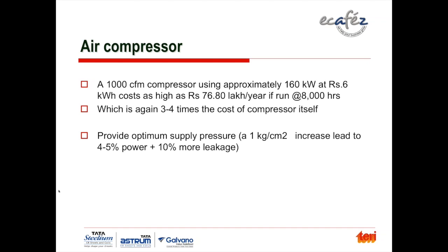We have done audits in many plants, even large plants, where they usually operate the air compressor at the pressure which was set at the time of commissioning. They have never bothered to check whether they require that much pressure at all in the plant or not. So this is one of the most common areas of energy saving.